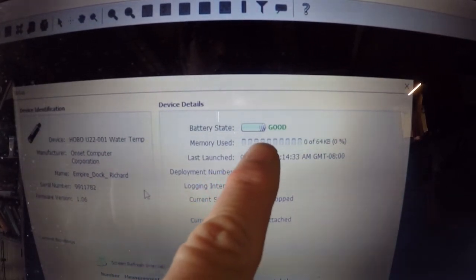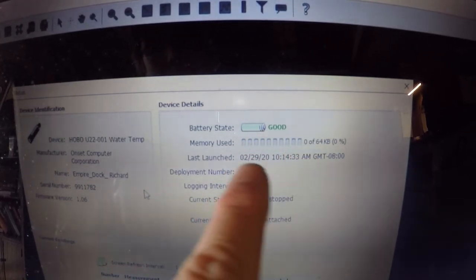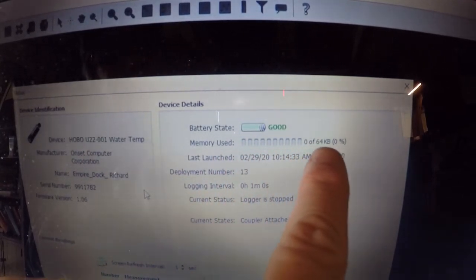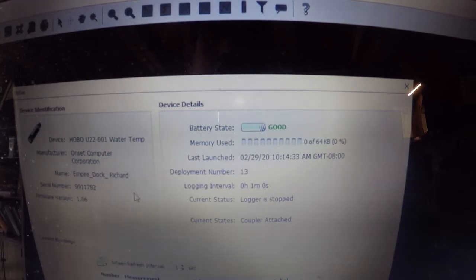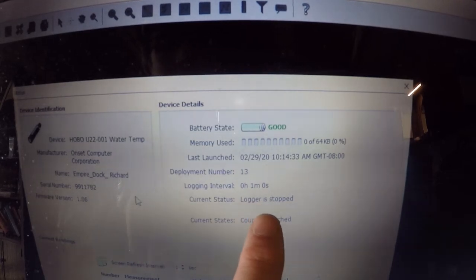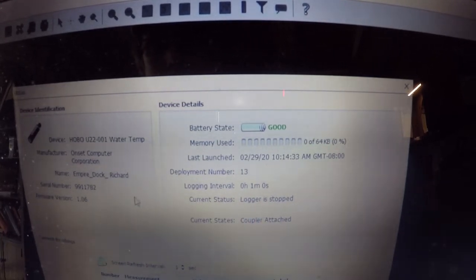One of the important things up here is to check for the battery status. It says good. Memory used is the next one, and this has 0 out of 64 kilobytes. So these are older probes, so they don't have a lot of memory in them. And it tells you other things like the last time it was launched, the deployment times, and one of the important things is right here, which is logger is stopped. So you want to be sure to look at that, because if it says the logger is active, that means it was put away without being stopped, and you're probably not going to have much of a battery left. Okay, so we've checked the status.